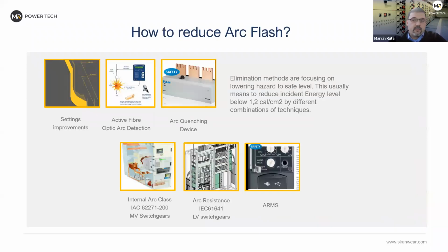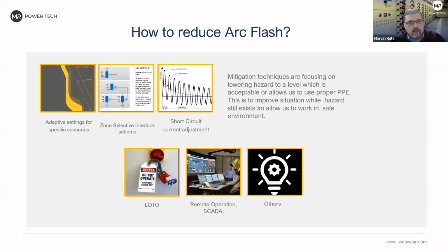And since we don't have a lot of time today, I will just try to highlight mitigation techniques that we can utilize in the passive and active solutions. Obviously you can see that we have settings improvements. There's a base cost-effective solution. We have fiber optic arc detection, arc flash relays. We have arc quenching devices, and also ARMS, arc flash reduction maintenance switch on the low voltage part. We also can build our switches according to the Internal Arc Classification for the medium voltage and arc resistant for the low voltage. So that helps.